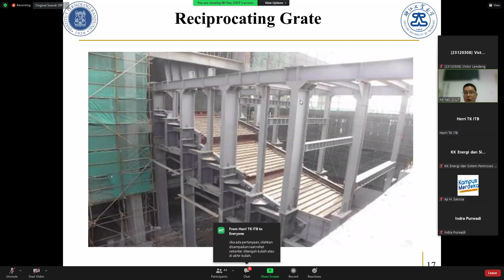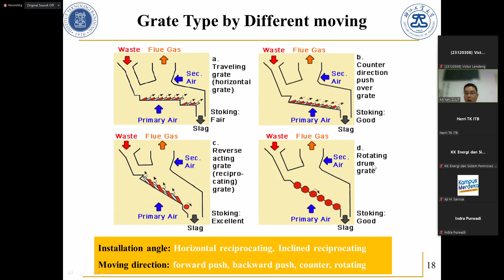So this is the typical reciprocating grid. For the grid, there are also different kinds depending on the installation or the movement direction. So this is a horizontal grid. You can see the waste on the grid is horizontal, and all the movement direction is forward, following the flow of the MSW, and this is counter. So for the different grid pieces or bars, the direction is counter, and this is reverse. What does reverse mean? Reverse means the movement of the grid is opposite to the flow of MSW. So MSW goes down, but the grid goes up in this direction. So this we call the reverse and the rotating.